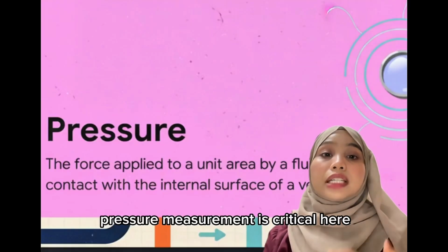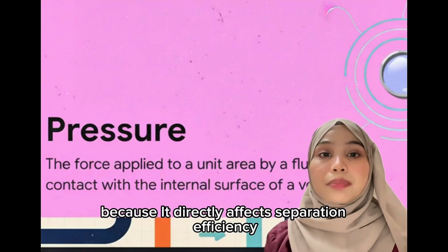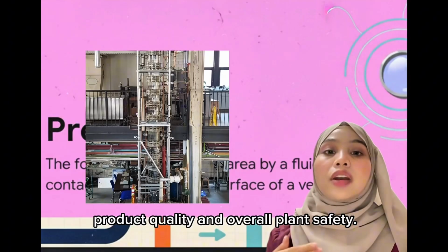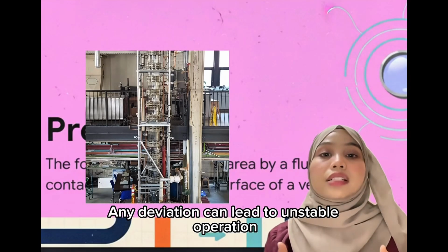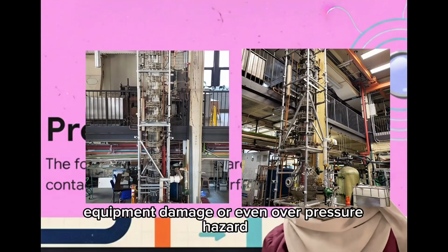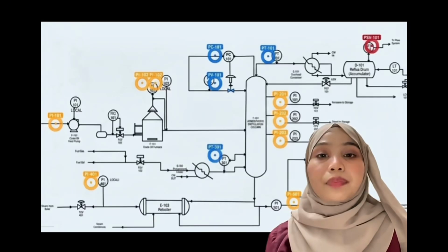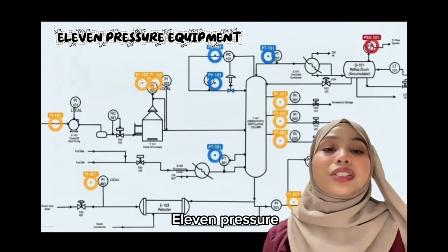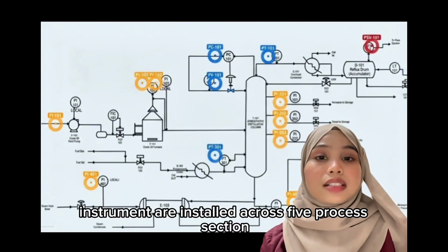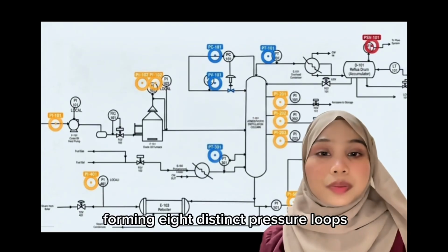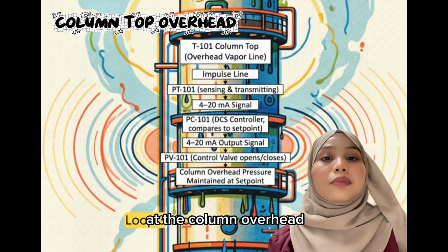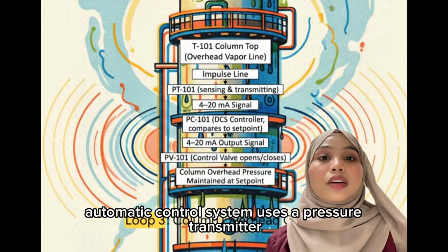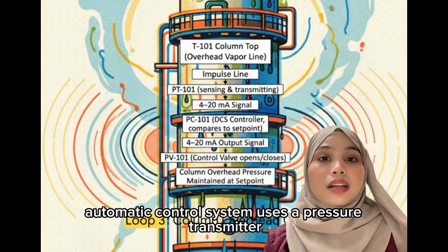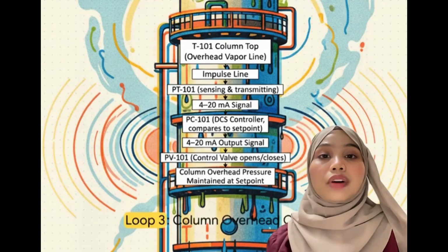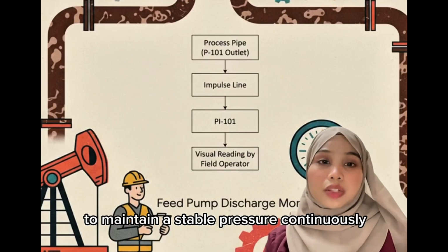Pressure measurement is critical here because it directly affects separation efficiency, product quality, and overall plant safety. Any deviation can lead to unstable operation, equipment damage, or even overpressure hazards. Across the unit, 11 pressure instruments are installed across 5 process sections, forming 8 distinct pressure loops. At the column overhead, a closed-loop automatic control system uses a pressure transmitter, a controller, and a control valve to maintain a stable pressure continuously.